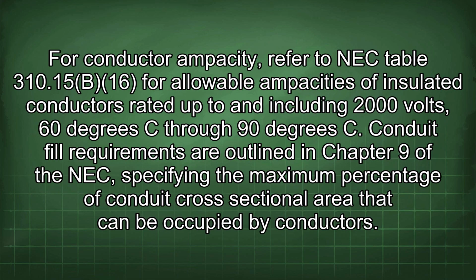For conductor ampacity, refer to NEC Table 310.15(B)(16) for allowable ampacities of insulated conductors rated up to and including 2000 volts, 60 degrees C through 90 degrees C. Conduit fill requirements are outlined in Chapter 9 of the NEC, specifying the maximum percentage of conduit cross-sectional area that can be occupied by conductors.